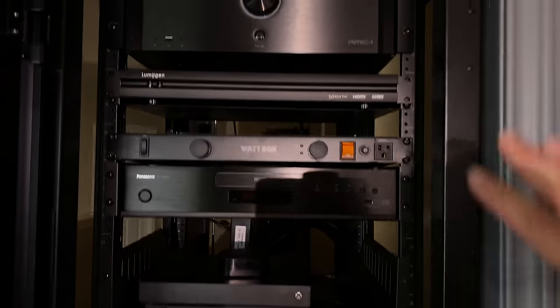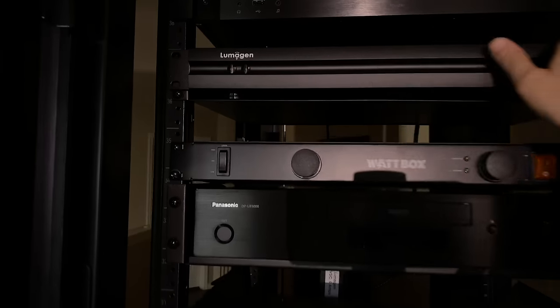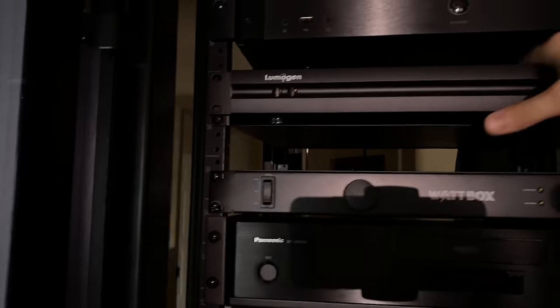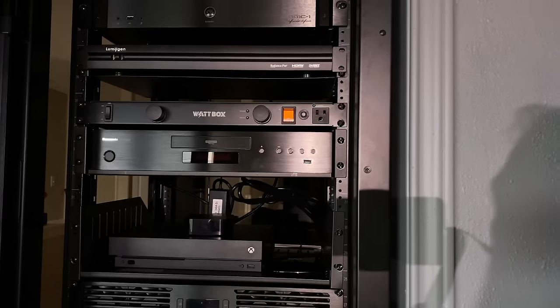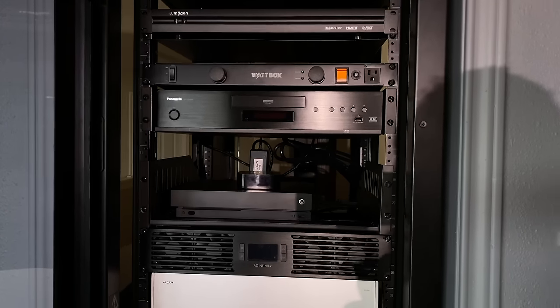Last thing that you guys saw, I made a big deal about the plates, right? So the blank plates that were going on here so that you couldn't necessarily stick your hand through it. It helps with thermal conductivity. It basically directs the airflow in one direction versus letting it jiggle all around in here, you know, an entropy. But that's another thing that I wanted to let you guys know about.